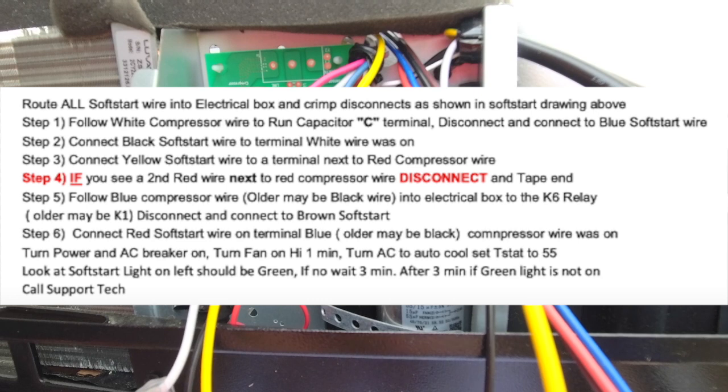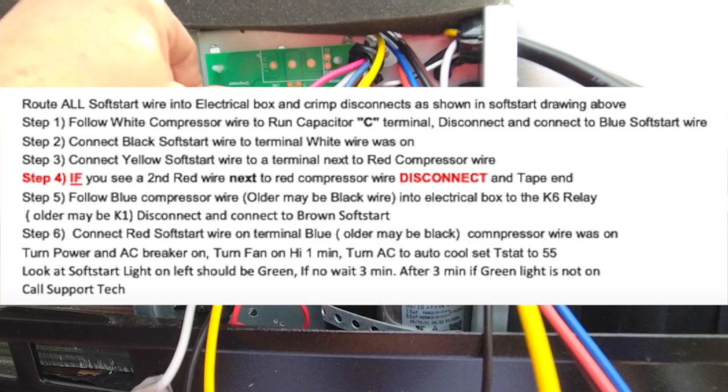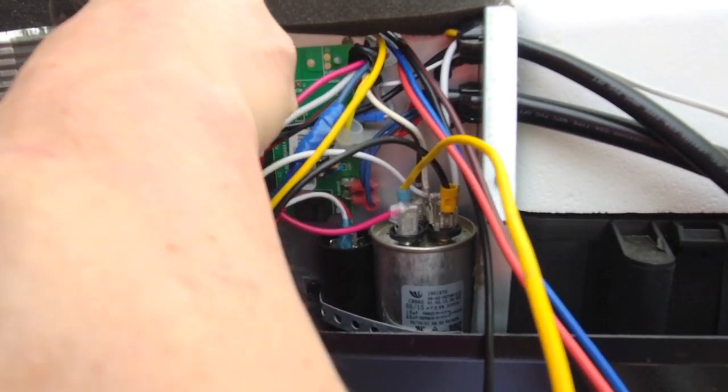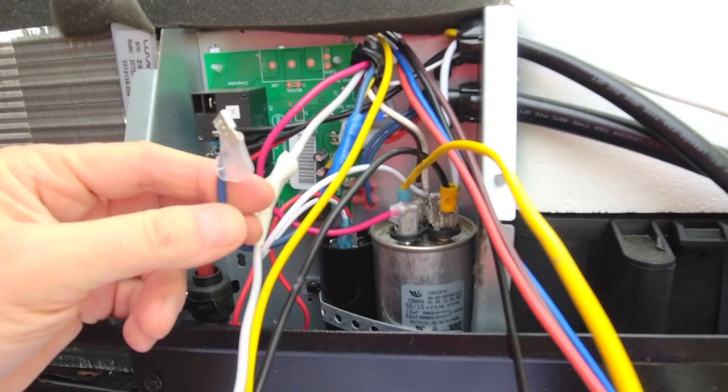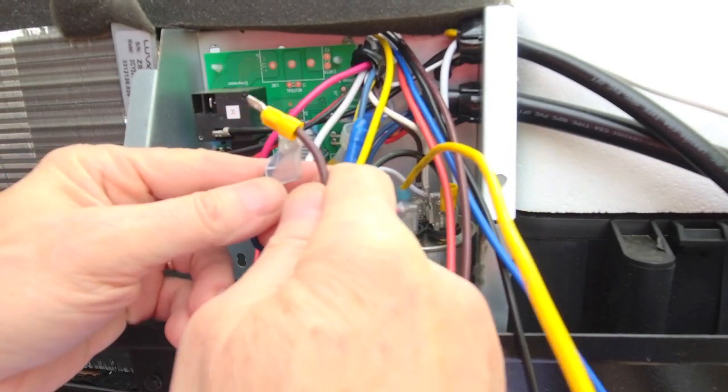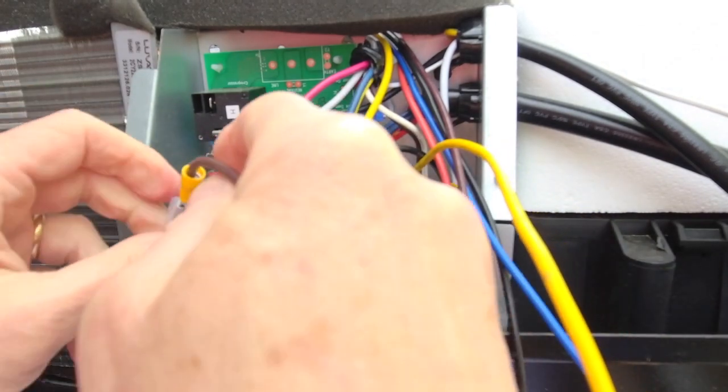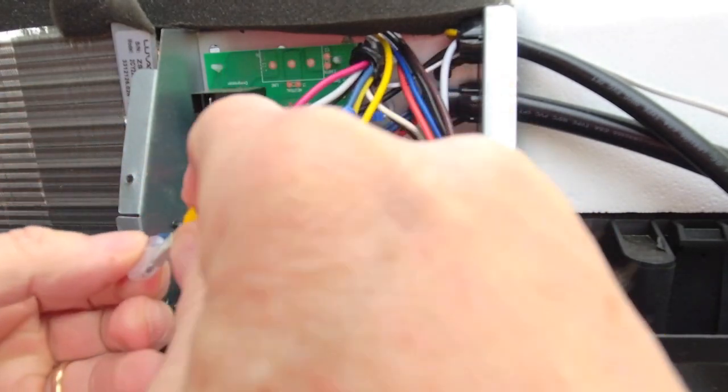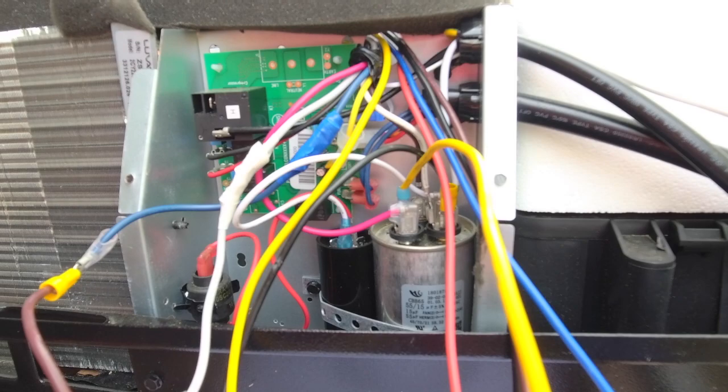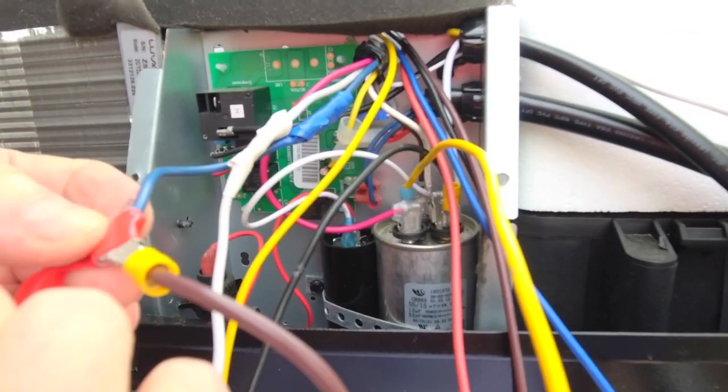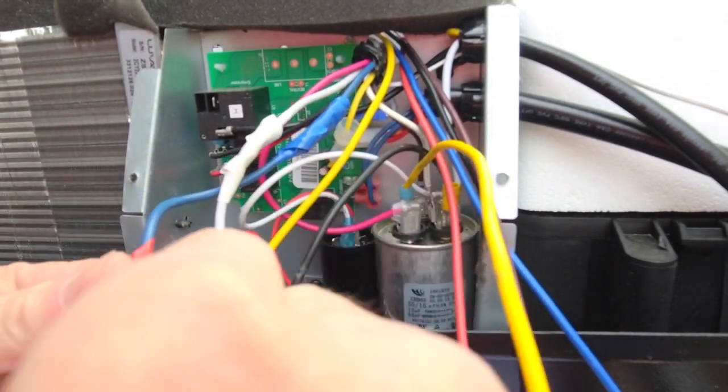Follow the blue compressor wire into the electric box into the K6 relay - that's this guy right here. Disconnect and connect it to the brown soft start. So we disconnect this. There's our wire right there. Here is our brown soft start wire. We'll connect those two together. That's all good. I'm going to put a little wrap of tape around there because I don't like bare things hanging out. That's always asking for trouble.